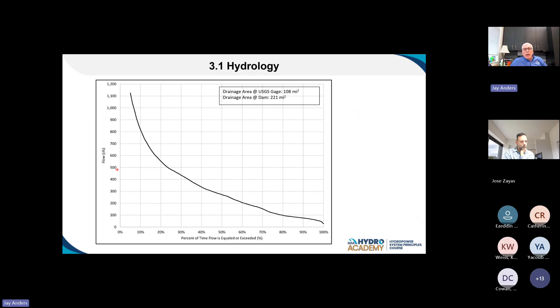Well, maybe that's where I should size it. But as soon as you do that, you end up giving up all this generation. So you can see we typically look at around 40%. That's a really good rule of thumb number to think about. So again, it's where we kind of look at that number and jockey back and forth based on the steepness of the curve, the shape of the curve, and how many cubic feet per second I can really get.